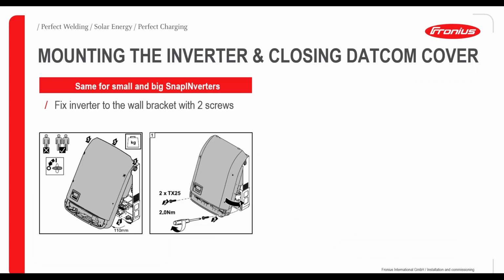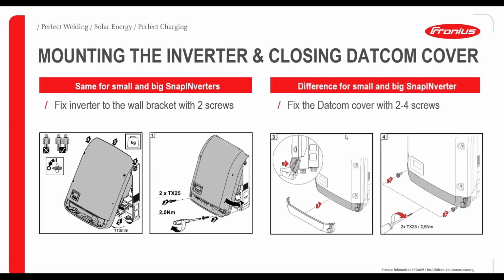Now that we've done the mounting plate and cabling correctly, we want to mount the inverter and close the DATCOM cover. Please make sure after you snap in the inverter to fix the 2 screws at the bottom. It's very important that the connections from the top part to the wall mounting are secured, so make sure to fix those 2 screws. After that, we can switch on the DC disconnector to the on position, and then close the DATCOM cover.